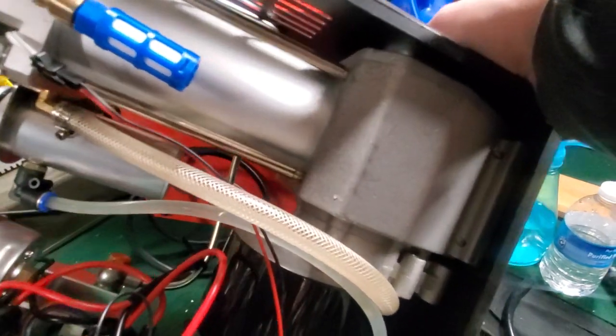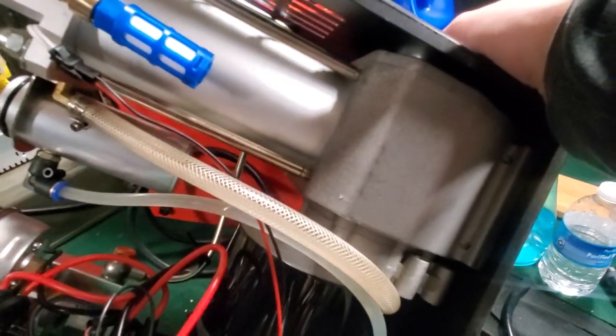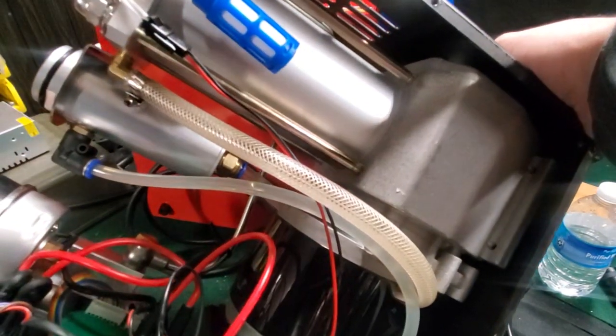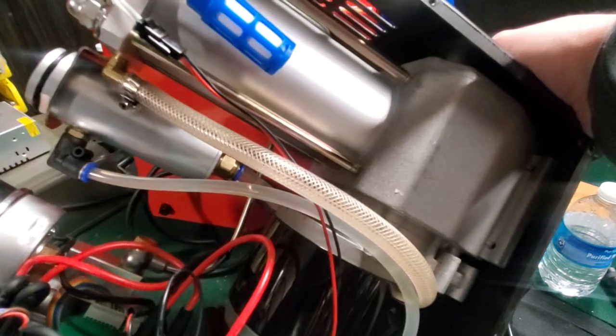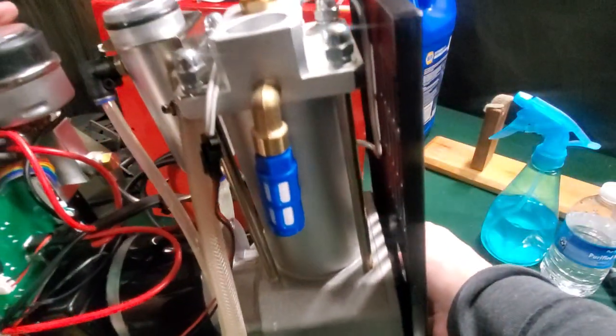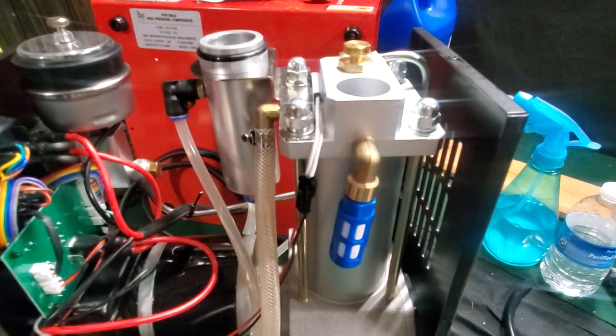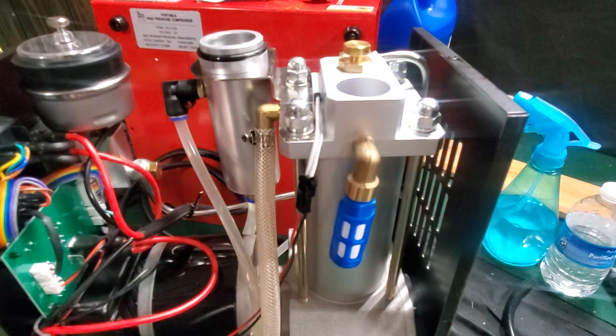You're going to get a lot of air coming out of there. Believe it or not, I've had a couple of these compressors where I've actually dropped almost 20 degrees temperature on them just by doing that, and it only takes 30 seconds.